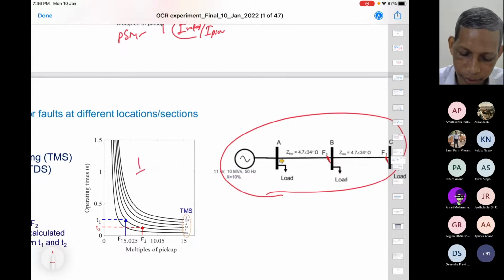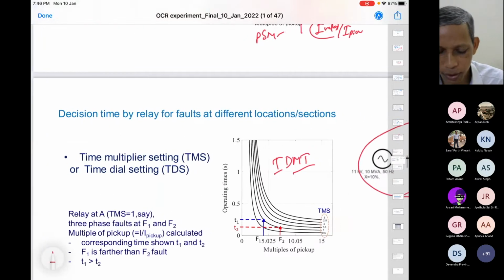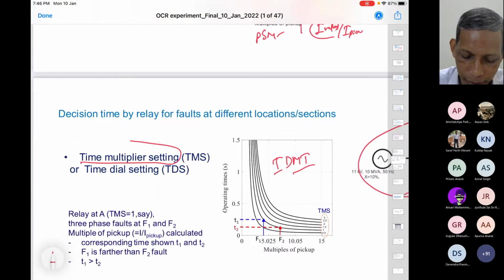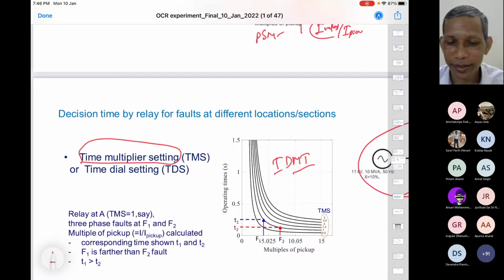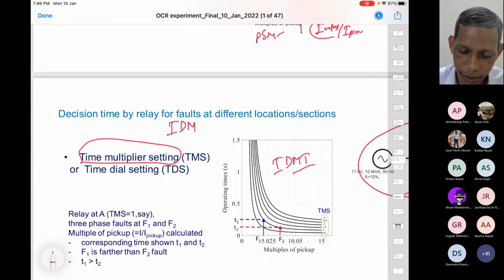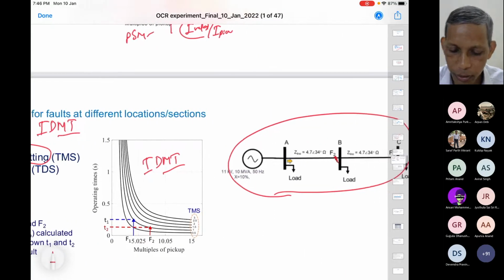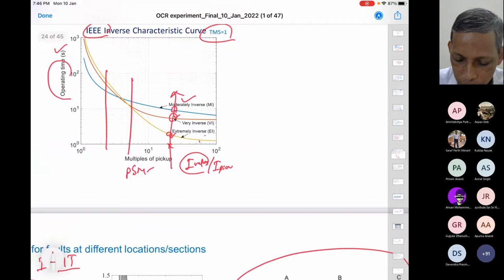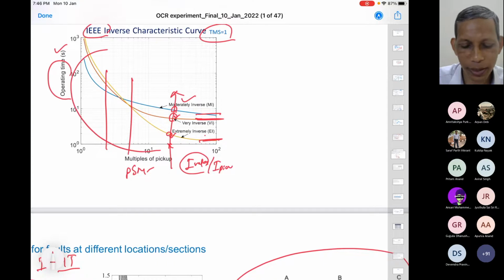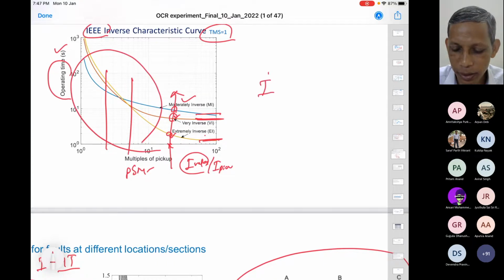So this is IDMT, and we have another option called time multiplier setting. The other settings are the pickup setting and the type of characteristic: inverse, very inverse, extremely inverse. There are three in the IDMT. In the IDMT we are talking about inverse definite minimum time. What is minimum time? I told you earlier. This is the minimum time. What is inverse? This part is inverse. Where is the inverse coming from? I squared t.